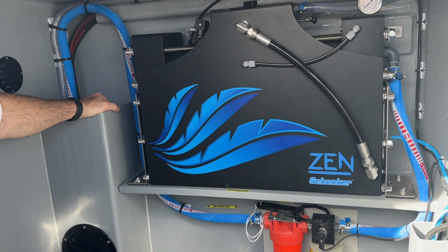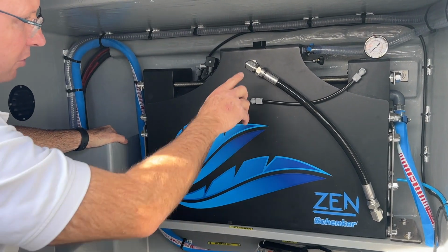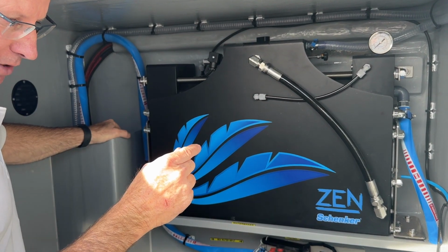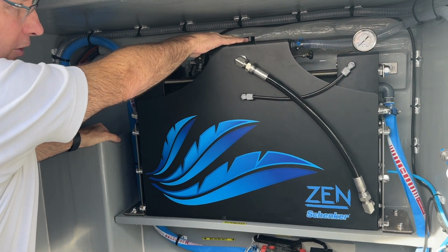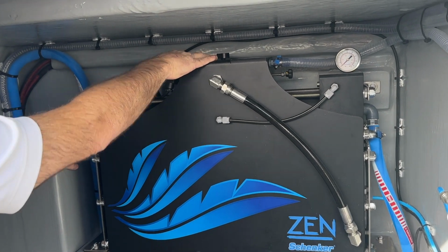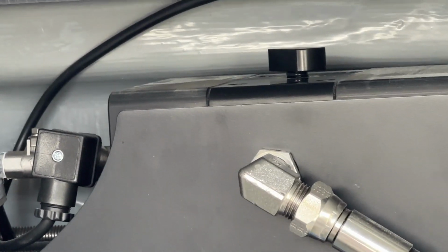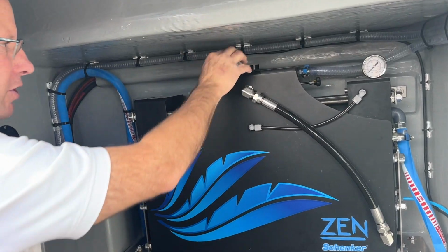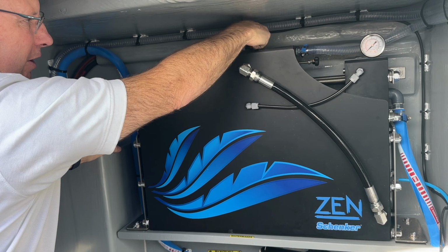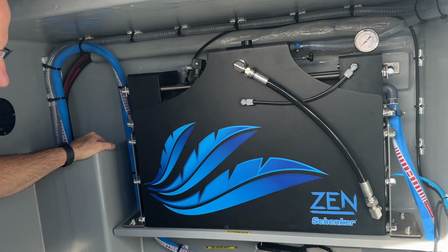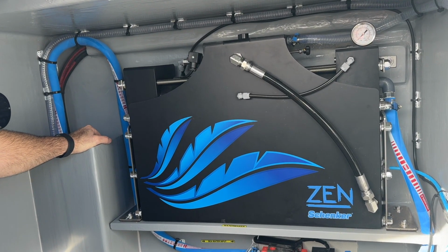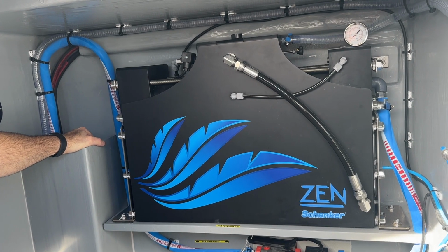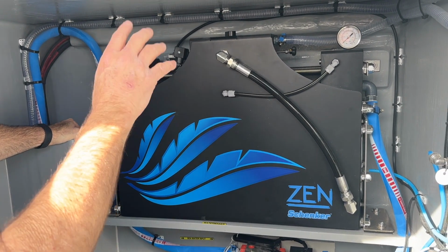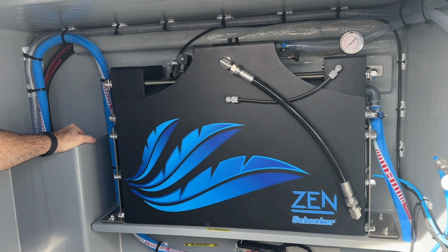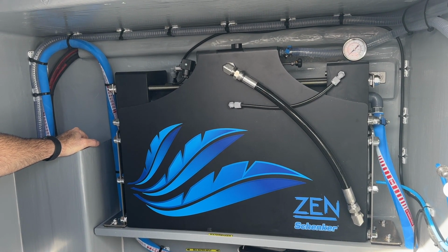Okay, and then we run the machine. Then you start up using the startup procedure, again with the decompression valve in the open position, until prompted 1 minute or so after the start of the automatic startup procedure to come and close this. You then close that in a clockwise direction. The automatic startup procedure takes about 2 minutes and will stop automatically. Once it stops, you can then start the unit with the normal start functions and make water.